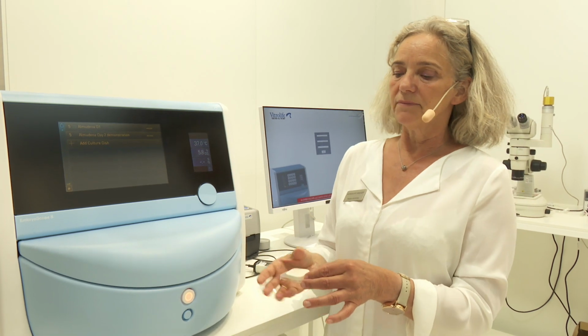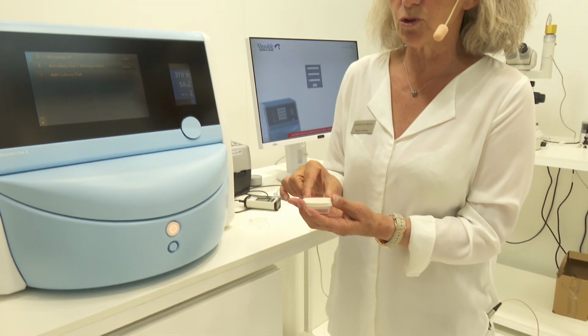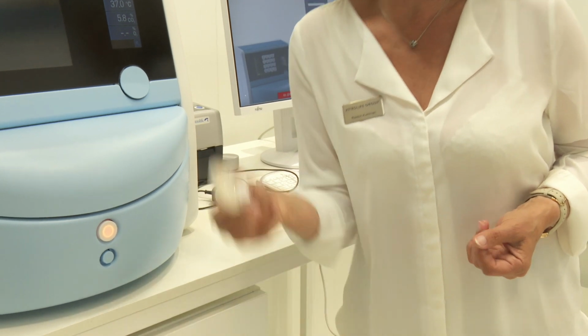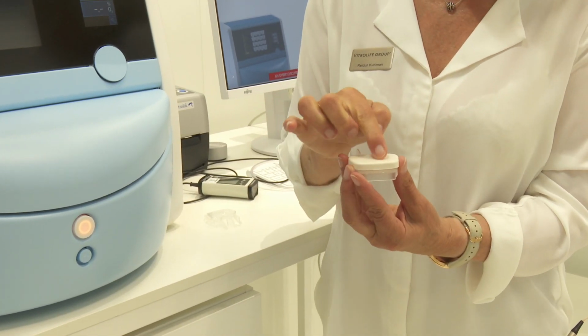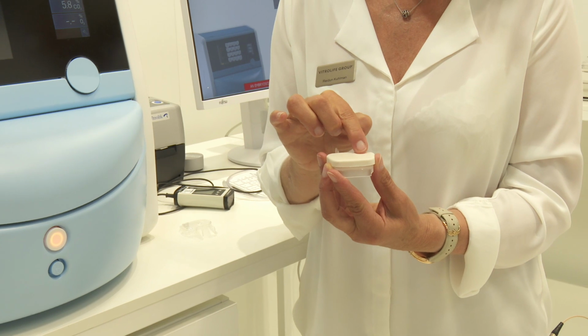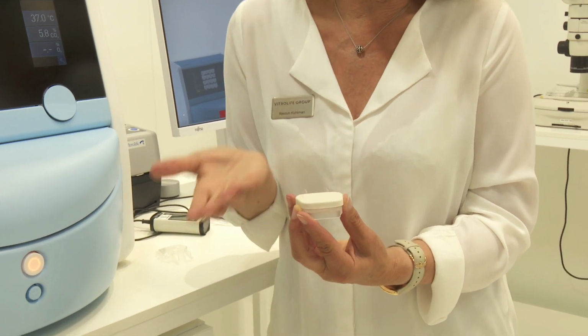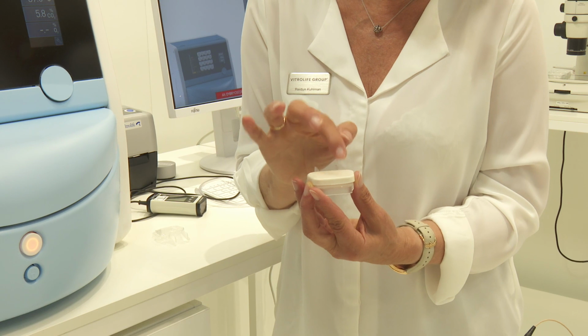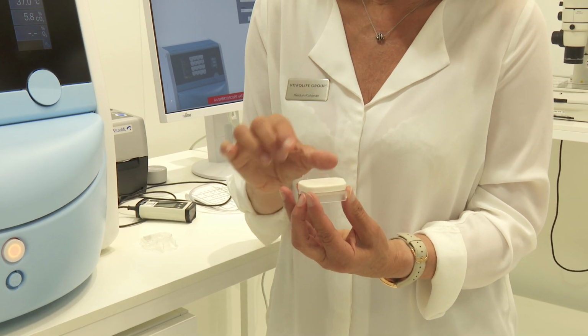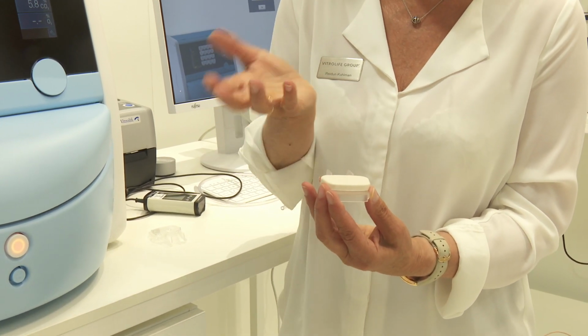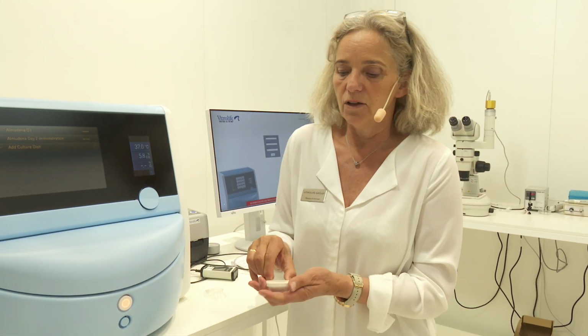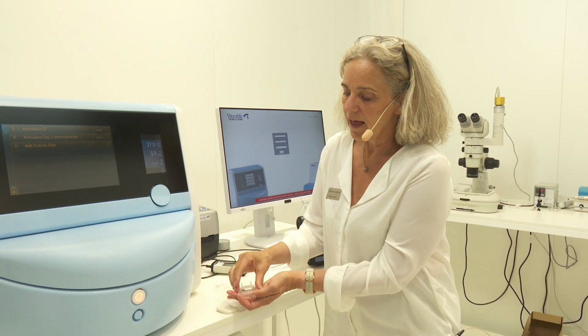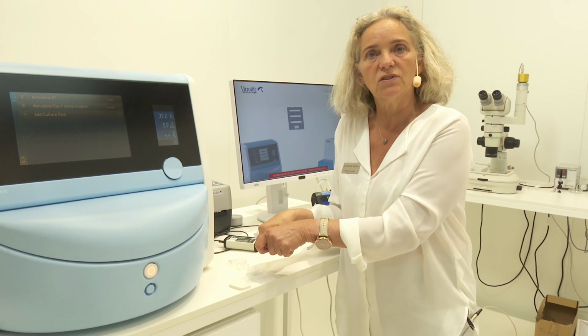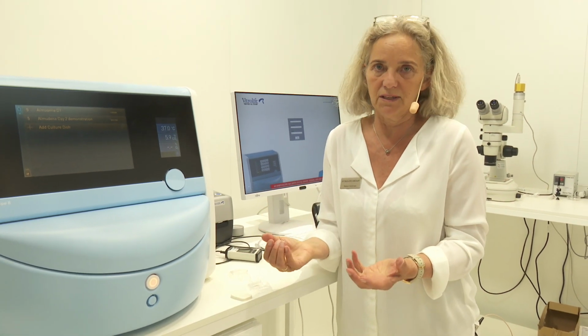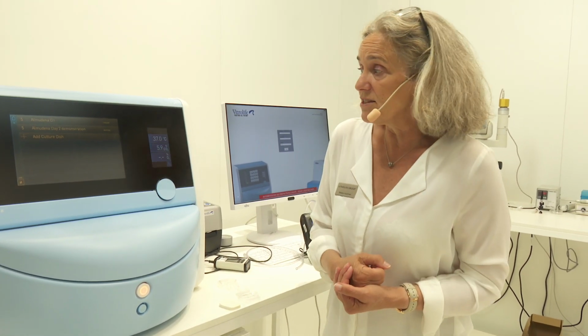You take it out, and what you do is that you turn it one time upside down. And it's because there are droplets formed on the inside of this lid. And to equilibrate it with the remaining medium, you just need to do this one time upside down. You take off the lid, and you put the microprobe directly into the dishes and perform the pH measurement. So that's actually what it is.